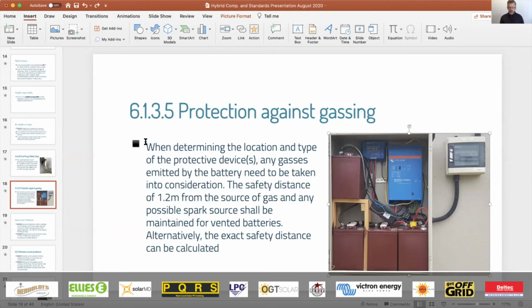And over here, it says in the standard, when determining the location and type of the protective device, any gases emitted need to be taken into consideration. The safety distance of 1.2 meters from the source of gas and any possible spark source shall be maintained for vented batteries. Definitely not the case in this crammed box. So that is something to take into consideration.